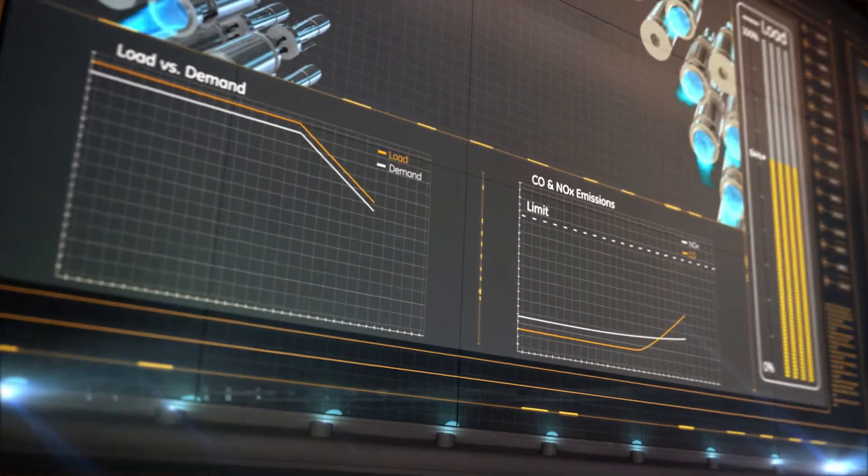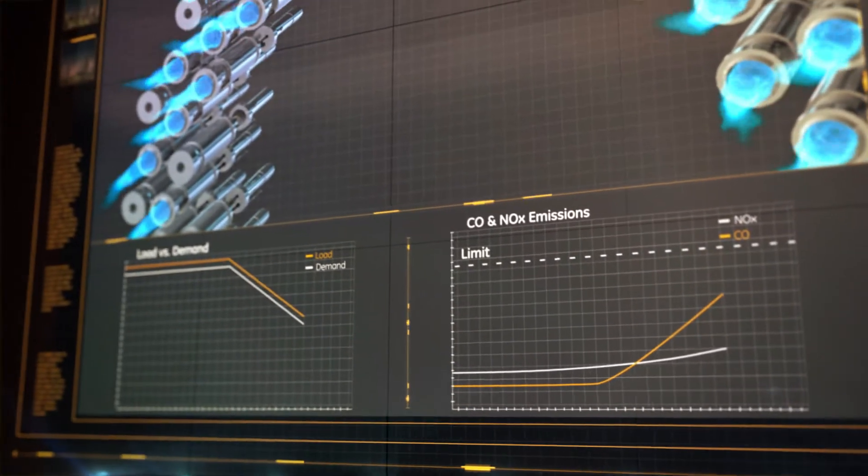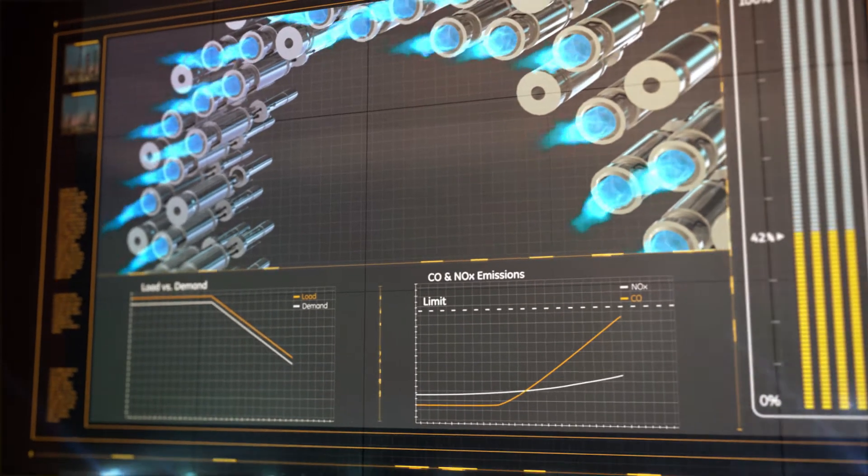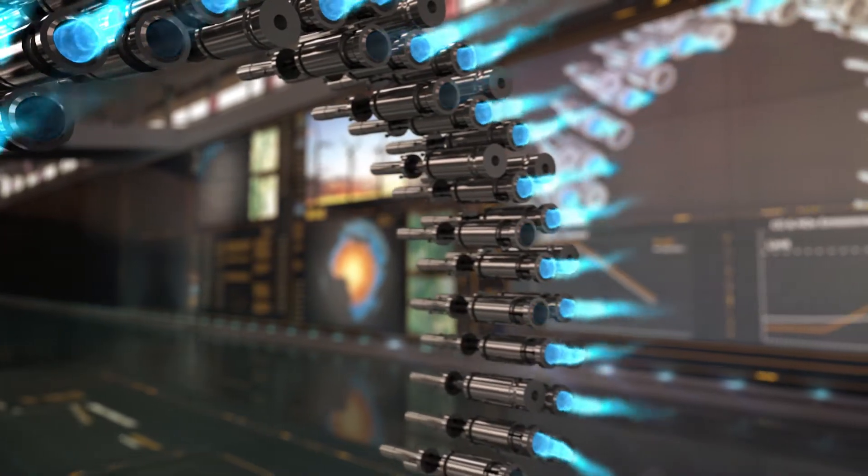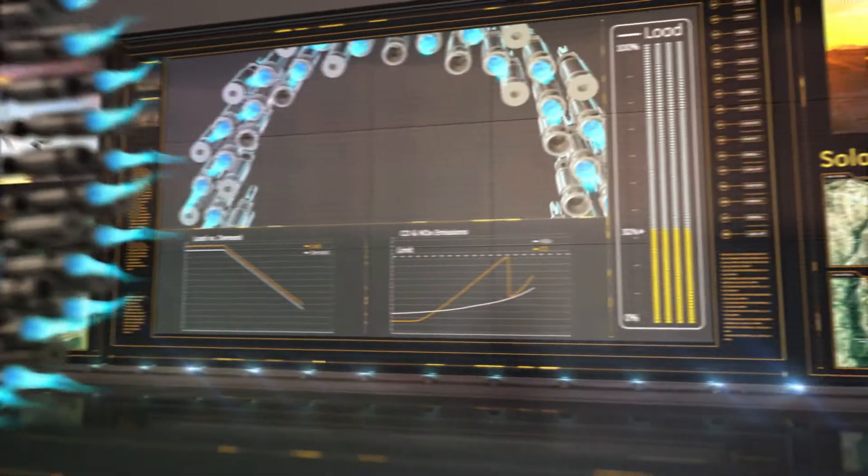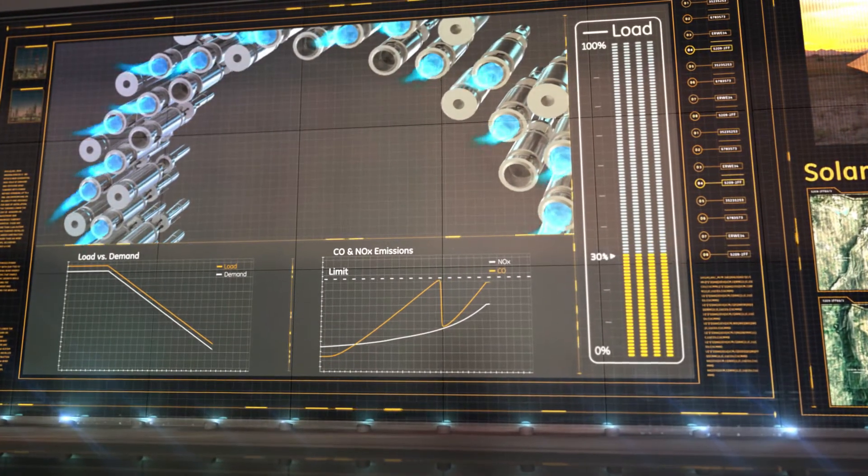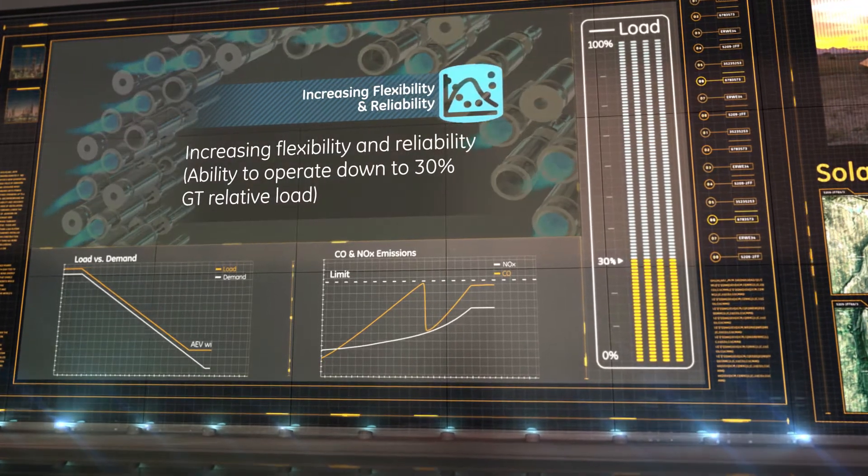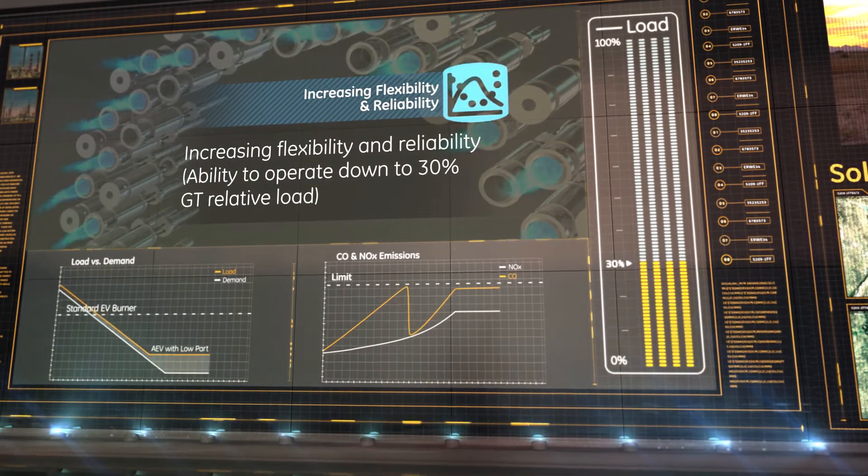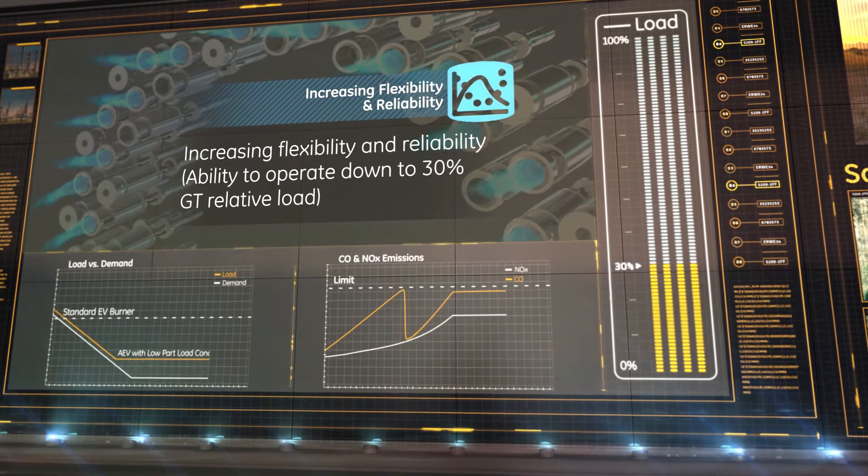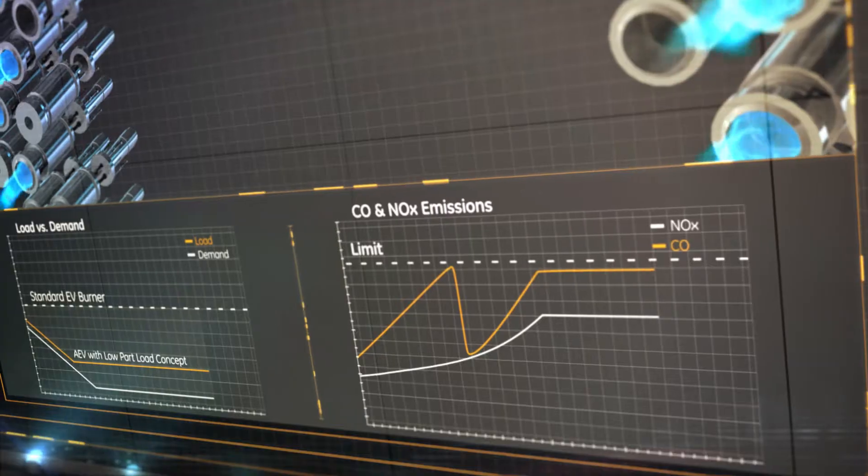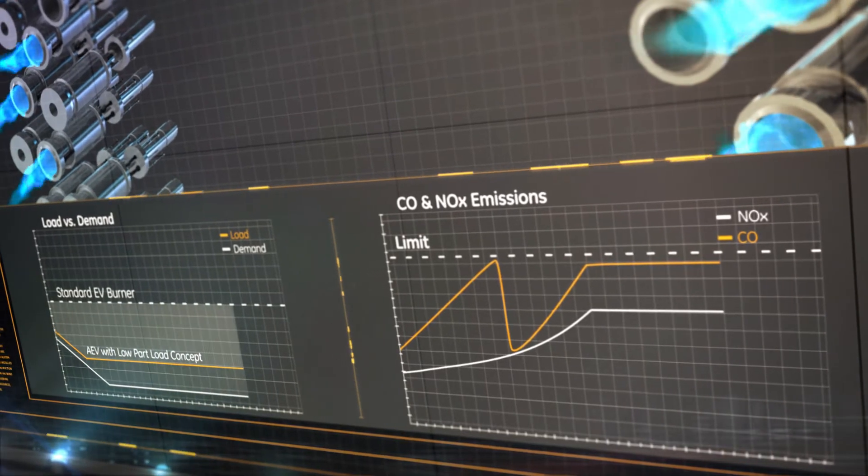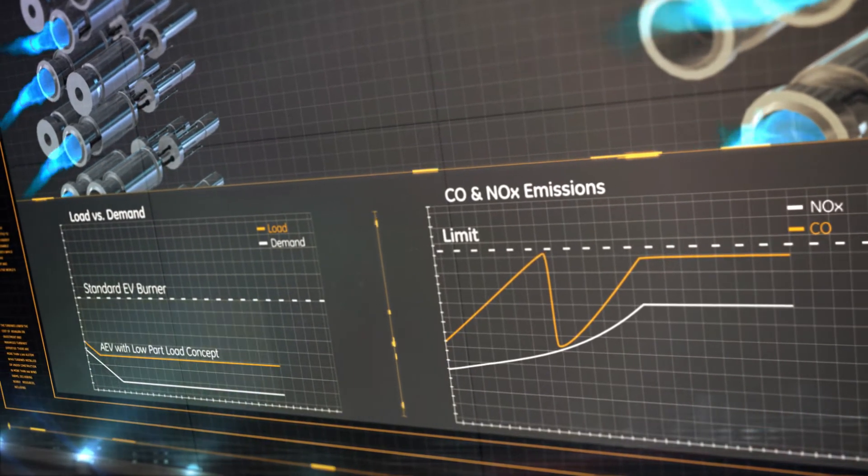With the AEV low-part load concept, as power output is reduced beyond 40% relative load, selected AEV burners are switched off to carefully control the flame temperature, allowing emission-compliant operation down to as low as 30% GT relative load. The unbalance between the power output and the power demand, potentially caused by environmental limitation, can be significantly reduced compared to the standard EV burner configuration.